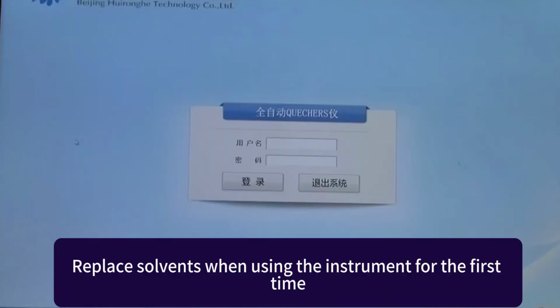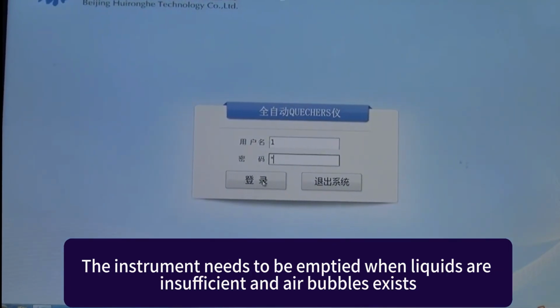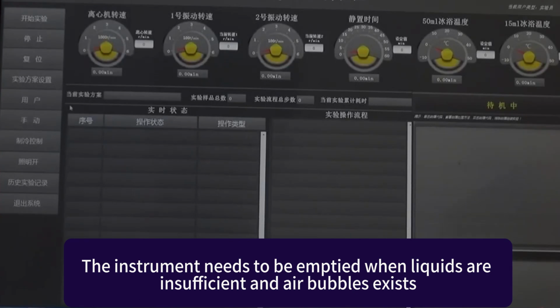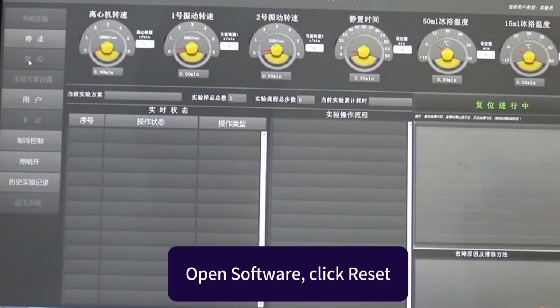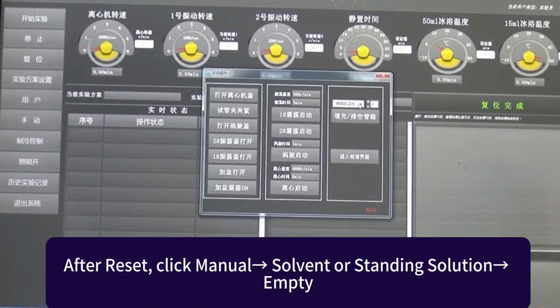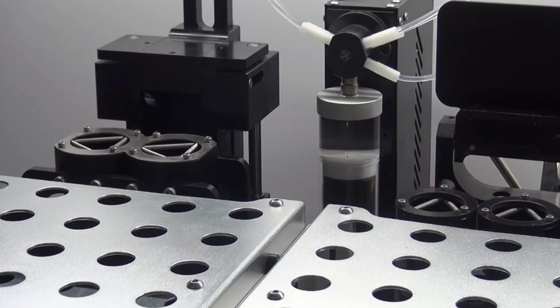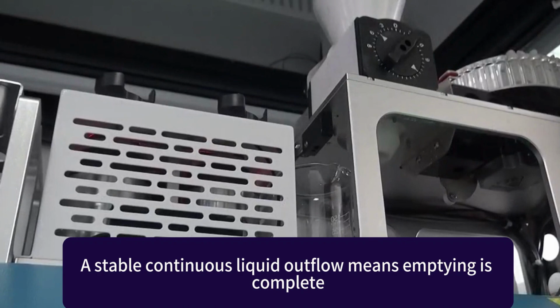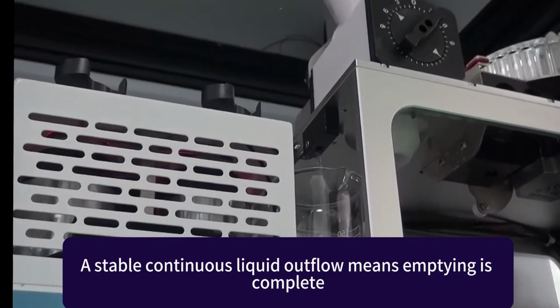Emptying. Replace solvents when using the instrument for the first time. The instrument needs to be emptied when liquids are insufficient and air bubbles exist. Open software, click Reset. After reset, click Manual, Solvent or Standing Solution, and Empty. A stable continuous liquid outflow means emptying is complete.